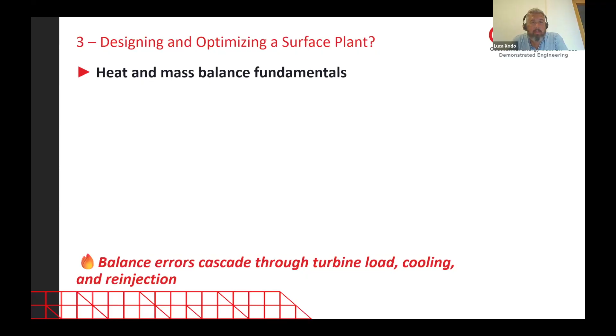So how do you choose how to design the cooling system? For example, if I have enough steam and I'm not using the brine, I can decide to use the steam itself, once condensed, as makeup water for a cooling tower. So I can have an ORC or a steam condensing plant with a cooling tower—provided I'm allowed to, in terms of temperature and pressure as we discussed before. If I can use that, I'll go for a cooling tower, because the parasitic loads are less than with a dry system.